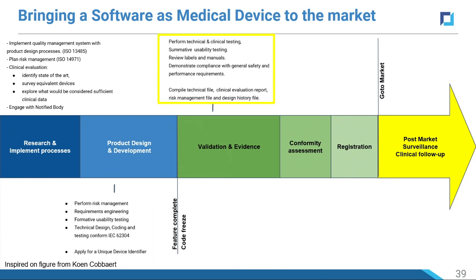Then you have a phase of the validation. So at the end of your product design and development, you should go for a freeze of features and also a code freeze, because then you need to go to validate. So the verification part is still part of the product design and development. The validation part is in the next phase. So there you will perform technical and clinical testing, summative usability testing. You will need to make manuals, and you will also need to prepare the labels that go with that.